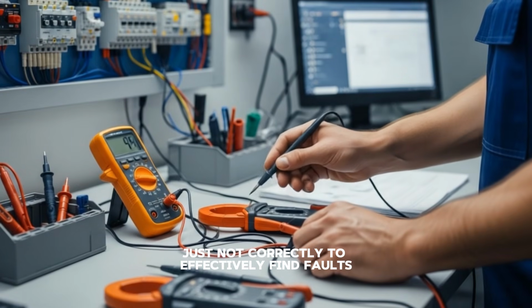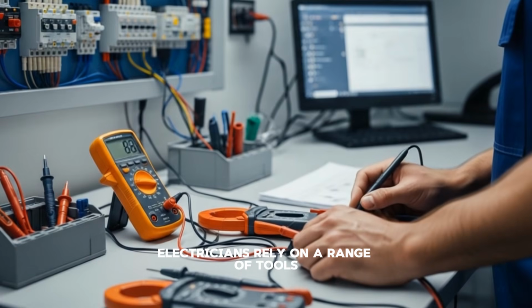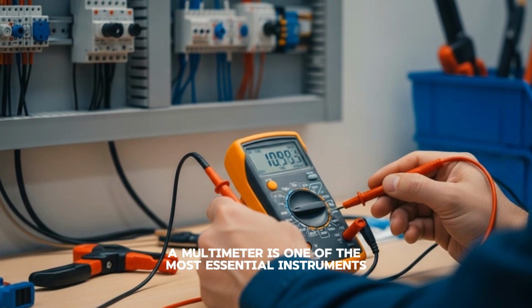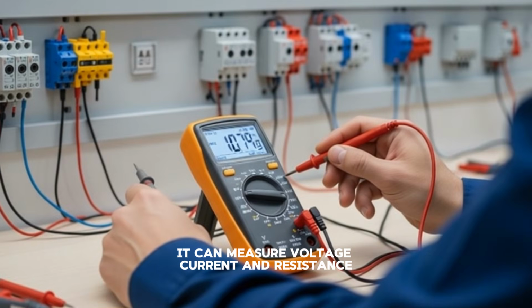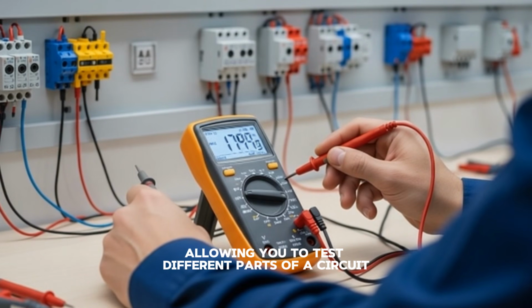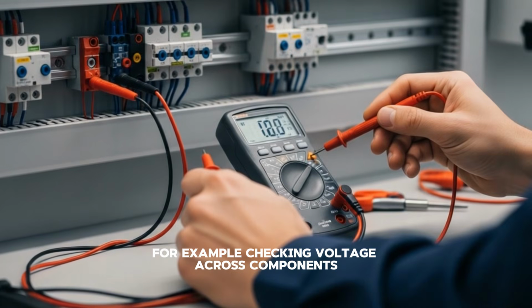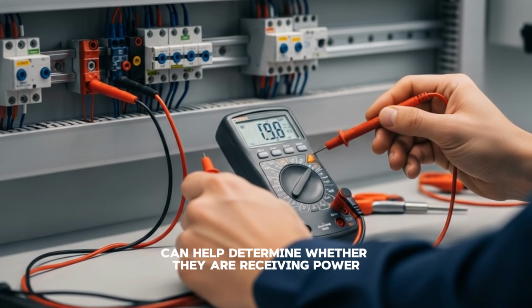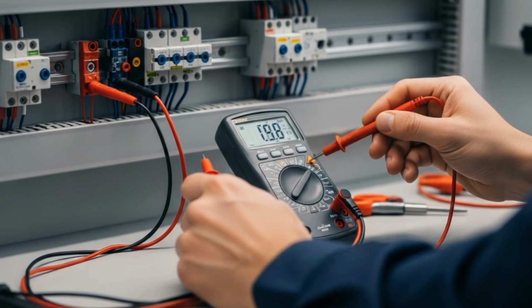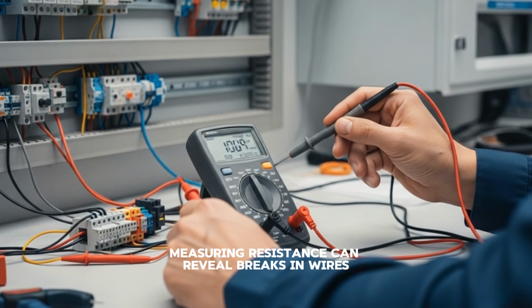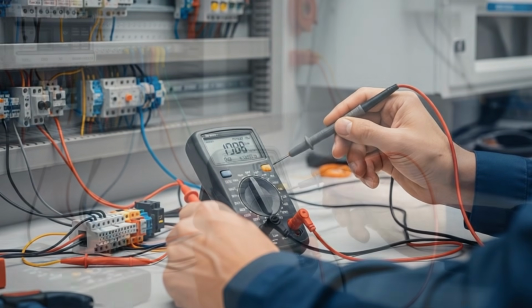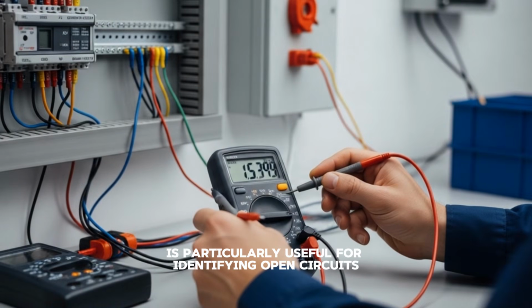To effectively find faults, electricians rely on a range of tools. A multimeter is one of the most essential instruments. It can measure voltage, current, and resistance, allowing you to test different parts of a circuit. For example, checking voltage across components can help determine whether they are receiving power. Measuring resistance can reveal breaks in wires or faulty components. Continuity testing is particularly useful for identifying open circuits, as it indicates whether a complete path exists.